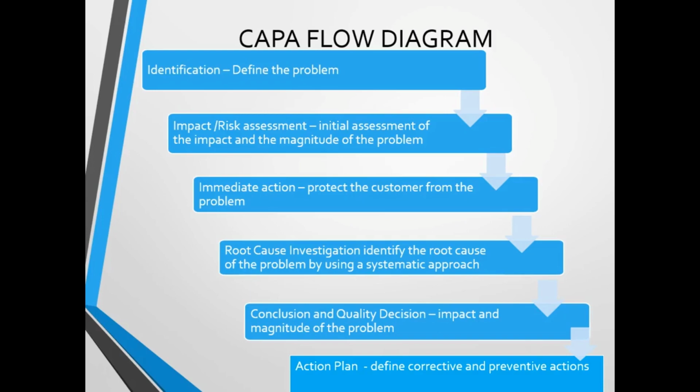So during those systematic approaches, you need to list all potential root causes and evaluate their likelihood, whether they're likely, possible, unlikely, remote, etc. And if more than one root cause is likely, then a simulation of the potential root cause may help to prove the actual root cause. But finding the primary root cause is essential to determine the appropriate corrective or preventative action.